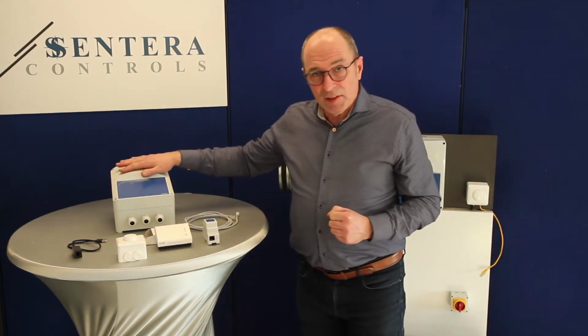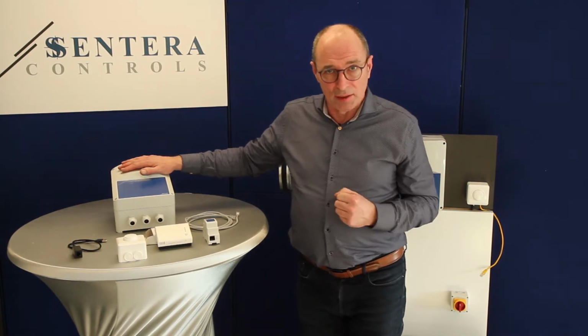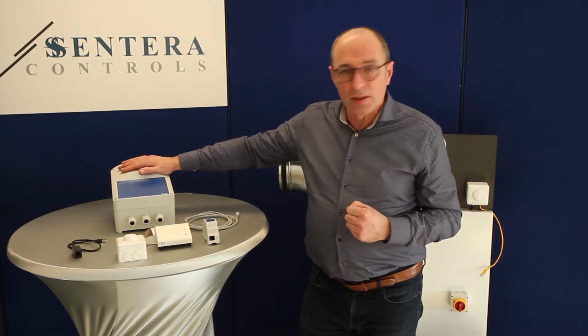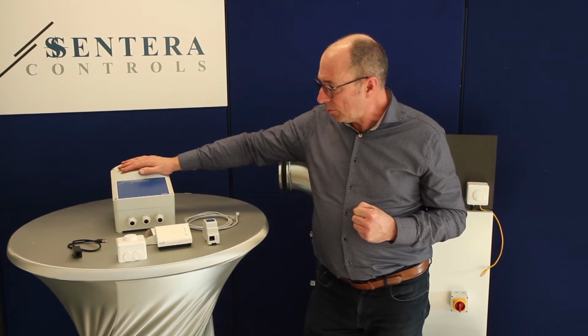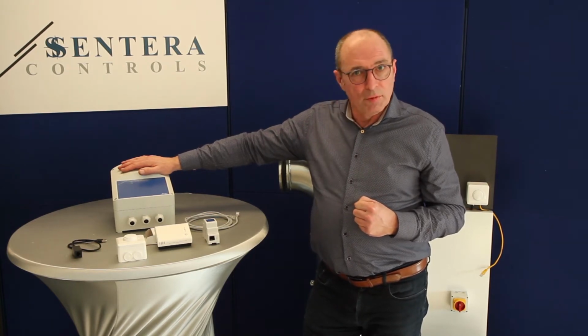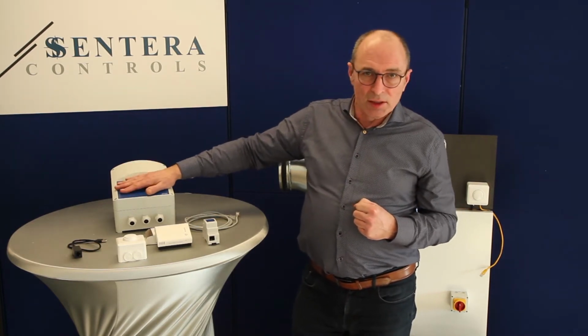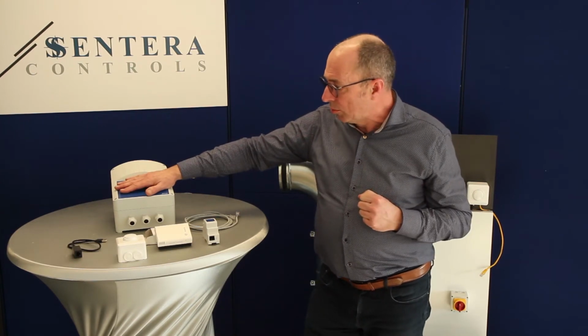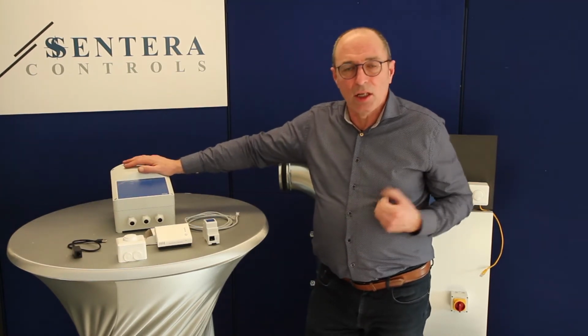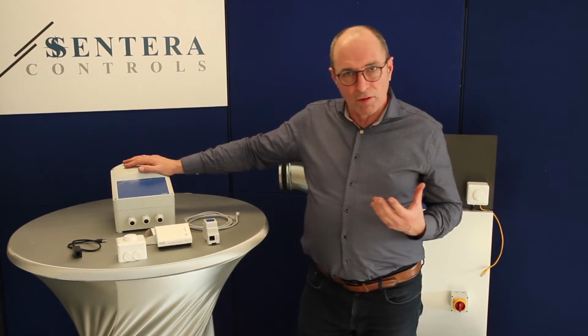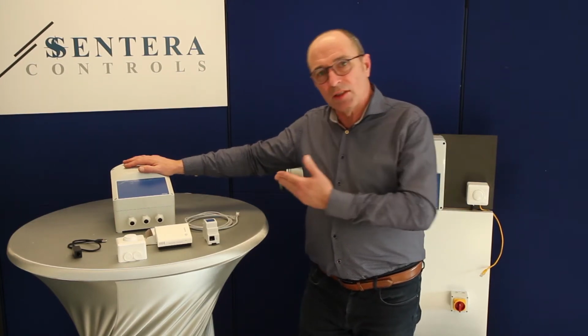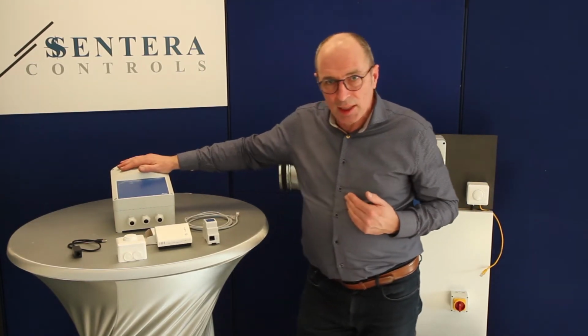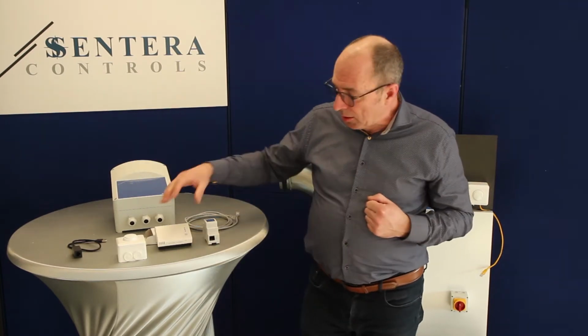The RTVS also works according to the principle of transformer fan speed control, but it is not equipped with a rotary knob. You need to operate it via a digital signal, Modbus RTU. That actually makes the device extremely suitable for demand-based solutions. This means that the position of the transformer fan speed controller will depend on, for example, a measured value that comes from a sensor.